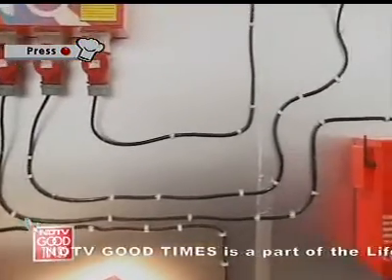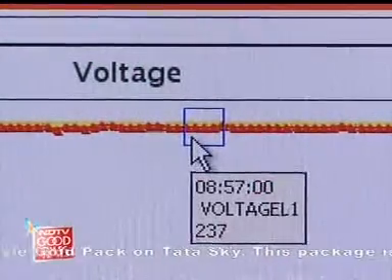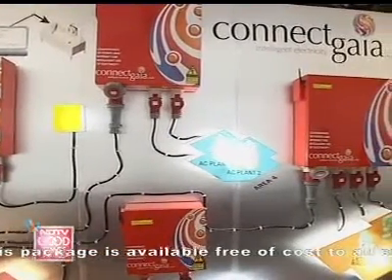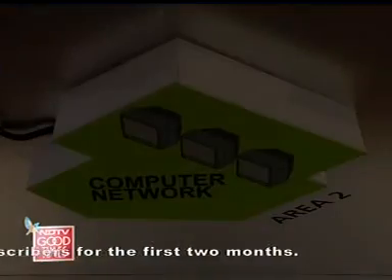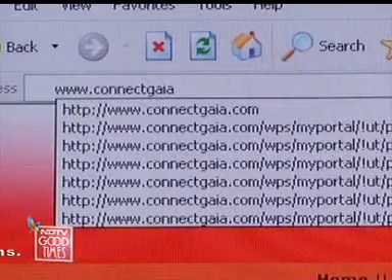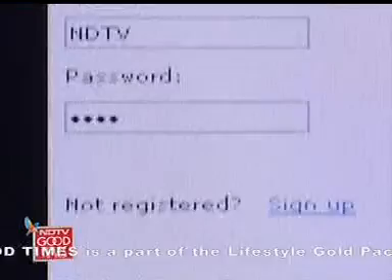The hardware comprising of mother units and child units are connected directly to the three-phase utility supply after the electricity meter. These units have power meters that measure electrical parameters both on inlet as well as the outlet. The unit outlets are connected to digital switches, enabling you to switch power on or off remotely. Data transmission between the units and the website is by an inbuilt GPRS. To measure, visualize, analyze, control and save energy consumption, you simply need to log into your personalized user account.